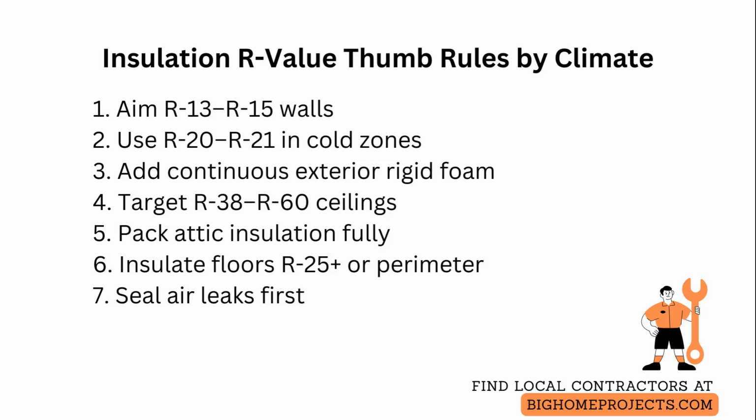are cold. For ceilings, target R38 to R60 in many regions because heat rises and attic insulation has the largest impact on annual heating and cooling loads.